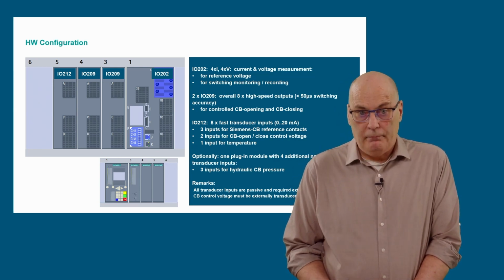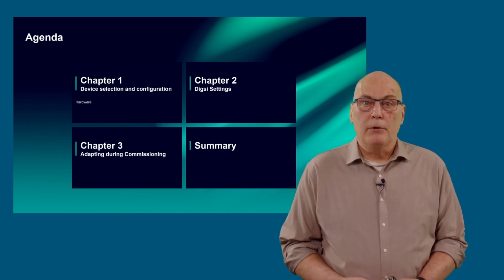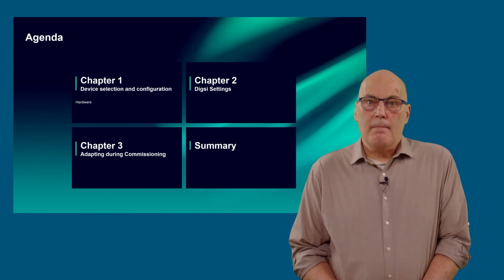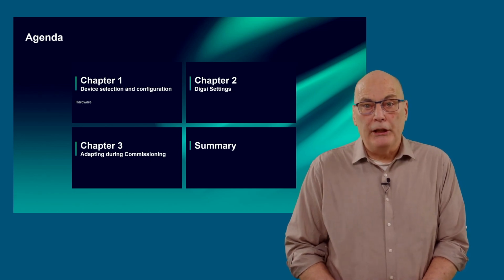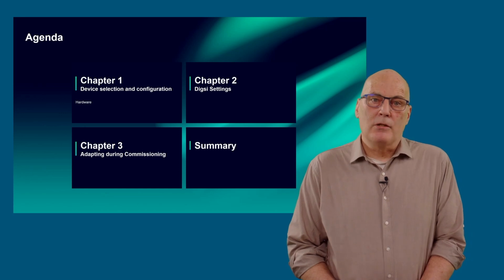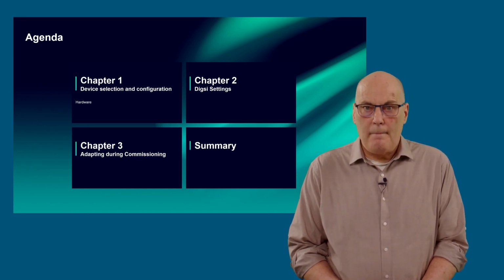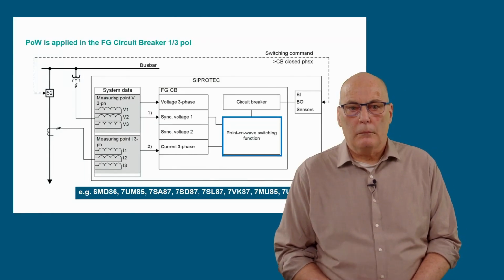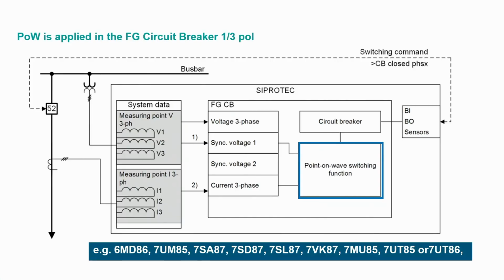This concludes Chapter 1, Device Selection and Configuration. We will now proceed with Chapter 2, DIGSI Settings. An outline of the settings required for a point-on-wave application will be covered, including some example setting calculations. The point-on-wave function is implemented in the function group circuit breaker with single pole, trip and close capability. It is therefore restricted to the device types listed at the bottom: 6MD86, 7UM85, 7SA87, 7SD87 and so on.